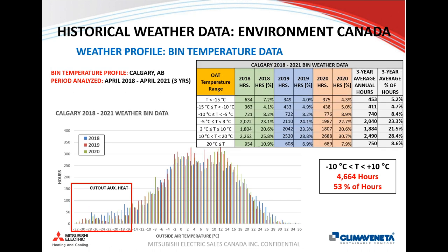Looking at Calgary, we see more extreme temperatures in the Prairie region. The three-year average for hours colder than minus 15 is about 450 hours, and time below minus 10 degrees Celsius is about 800 hours — roughly 10% of the time where you'd need an auxiliary heat source. But it's really about incorporating the heat pump into the design as best as you can. These types of projects shine when you want to reduce greenhouse gas emissions from your building.